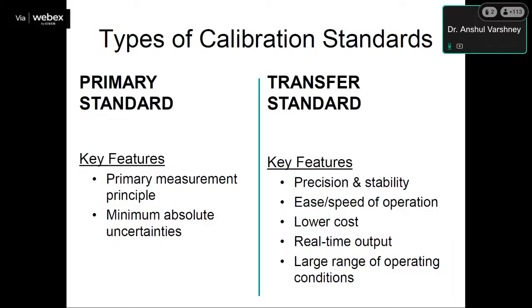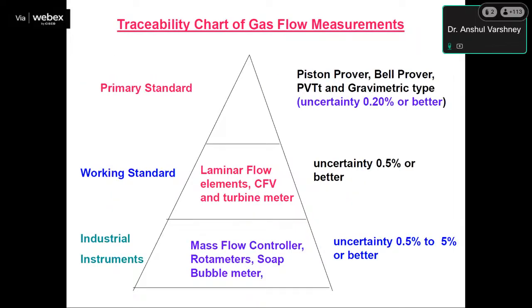So there are two types of calibration standards, primary standards and transfer standards. The key features of a primary standard: it uses the primary measurement principle, and there is minimum absolute uncertainty. The key features of transfer standards are precision, stability, ease of operation, lower cost, real-time output, and a large range of operating conditions. So basically, this is the traceability chart of the gas flow measurement system. The primary standards are piston prover, bell prover, and PVTt or gravimetric type method. Uncertainty is 0.20% or better. Working standards are laminar flow elements, critical flow venturi and turbine meters.